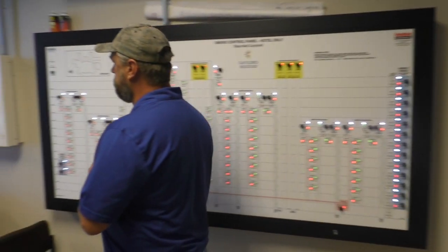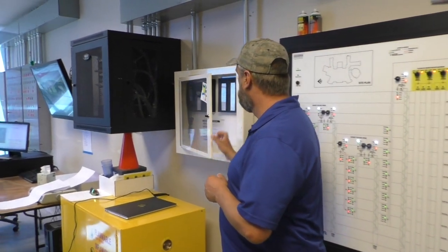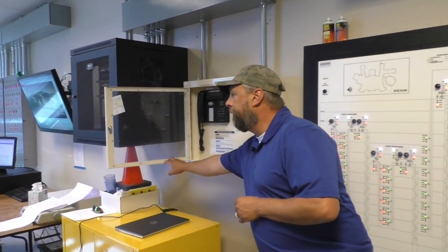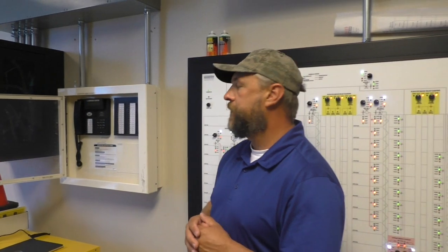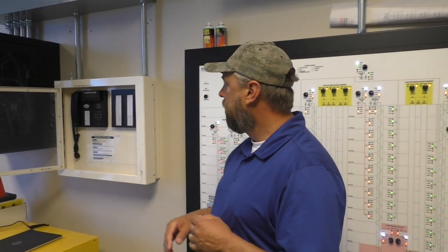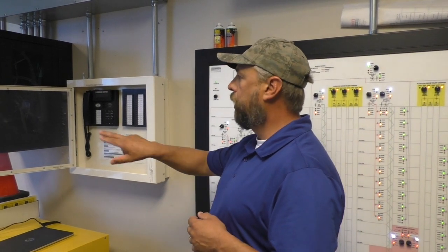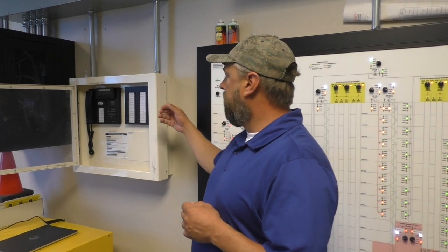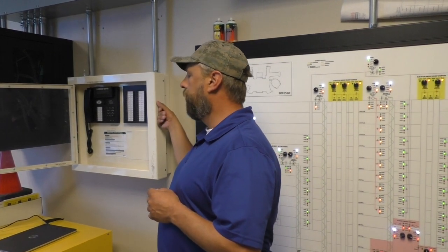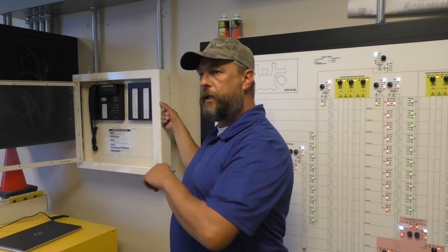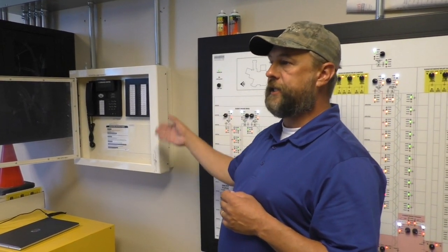Area of Refuge is a phone system that is used on every elevator lobby other than your main floor of egress, and also every 5th floor of every stairwell within the hotel. If somebody with ADA isn't able to utilize the stairs, they're going to push a call box outside the elevator lobbies or within that stairwell. You're going to get a phone call here first. The call box calls down here, and if nobody here picks up, it then calls our monitoring station, which then dispatches you.